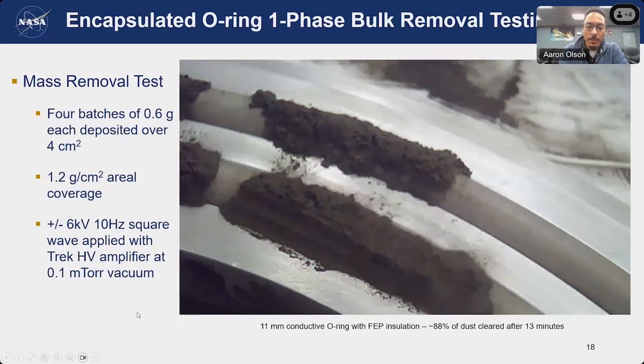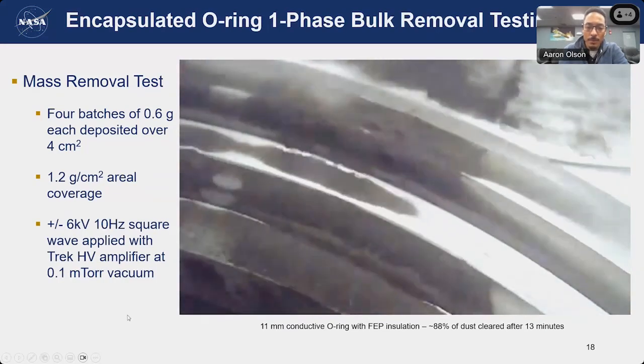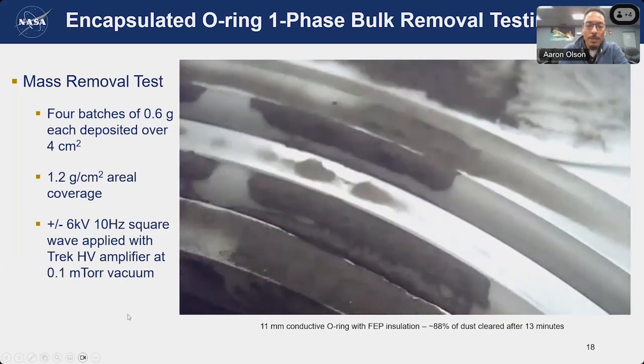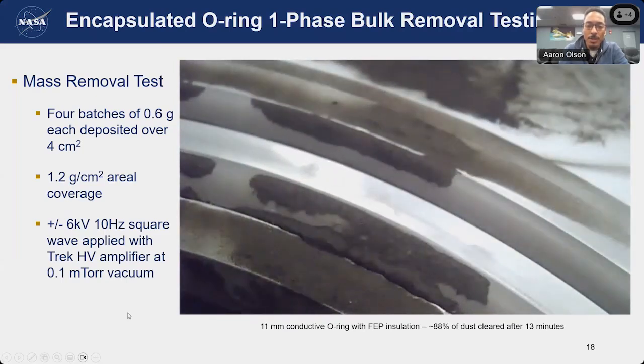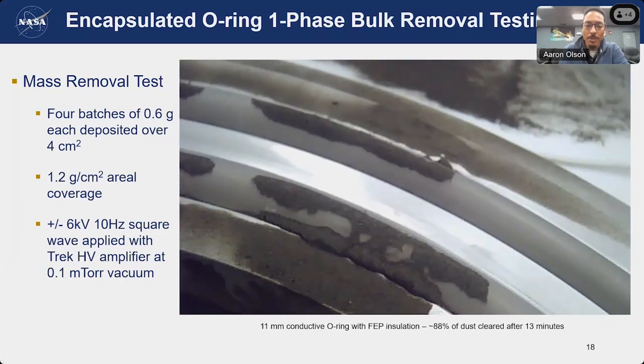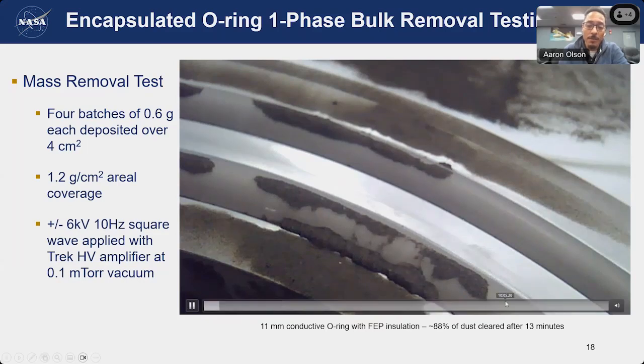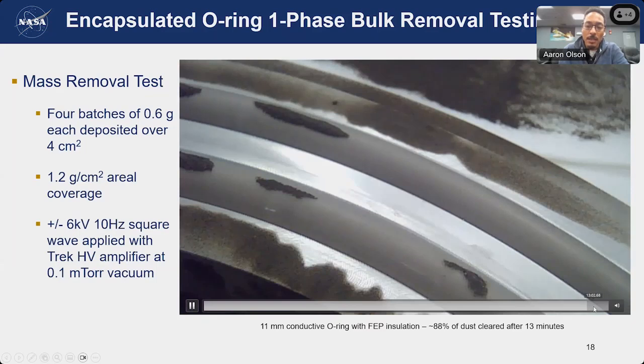So a lot of it is removed initially, but you can see here after the fact that the rest of it is taking a much longer time to eventually clear, especially at the apex of where the seals are. That's because the field is the weakest there at the top, so it's going to take a lot longer for the dust to eventually come off. But it does. If I fast forward this video toward the end here, after a little bit more than 13 minutes, you can see that most of the dust was removed. Not all of it, but most.